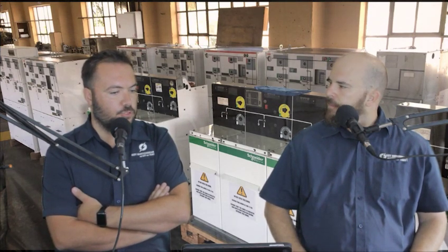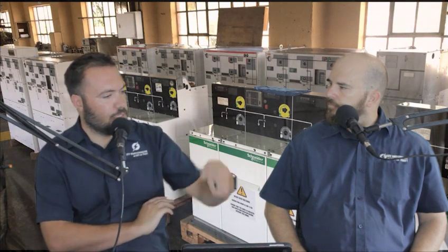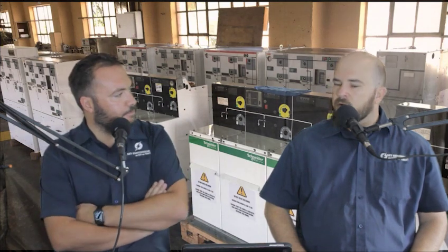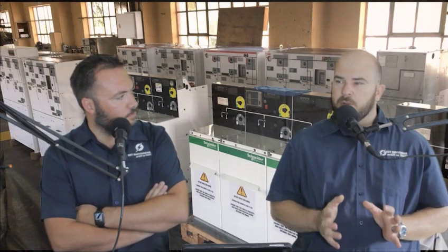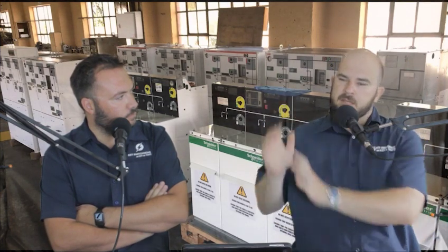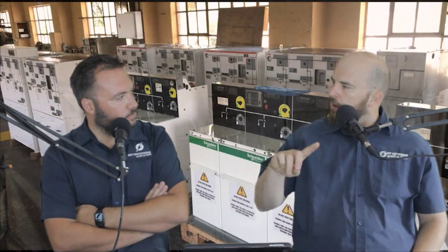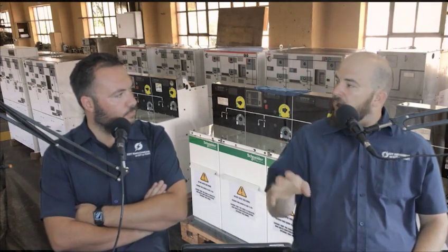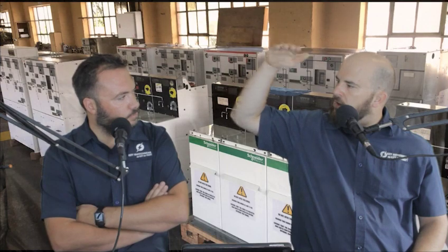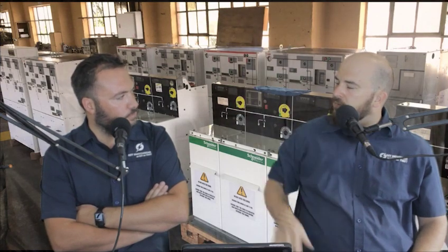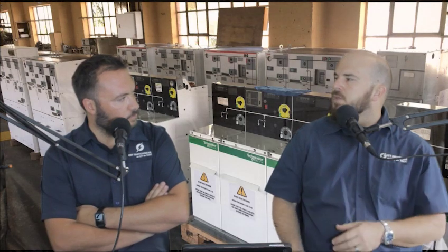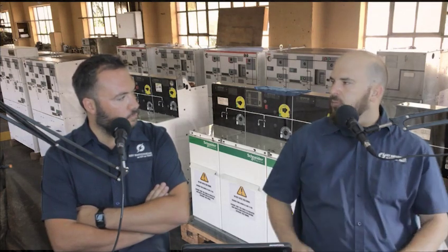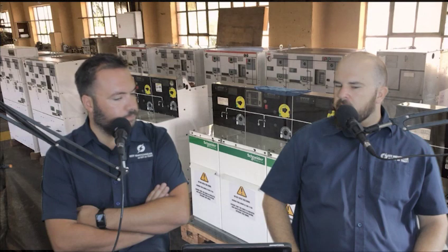What happens if you have too much insulation gas in your tank? Yeah, so obviously every tank has got design limits, and the big problem is when you go up above sea level. If you have quite a full tank and you go high above sea level, like 2,000, 3,000 meters, the tank can actually pop. So your rupture plate will rupture, or the tank itself will get damaged. So it's not a good thing.